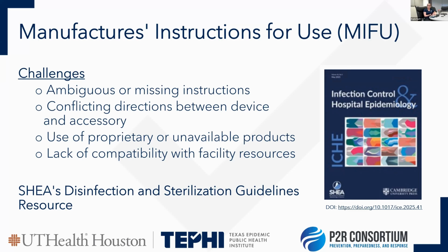Sometimes there are conflicts between a device and its accessories. So the main device says to clean, high-level disinfect, or sterilize one way, but then the accessory says a different level. For example, the device has to be high-level disinfected, but an accessory or a piece of adapting that you're using, such as a biopsy or another additional piece, says you only have to clean it. Well, that doesn't make sense, because that's a lower level of cleaning or disinfection than the main device. So you want to make sure that you know what's being added onto the device and that it's all at the same level or a higher level.